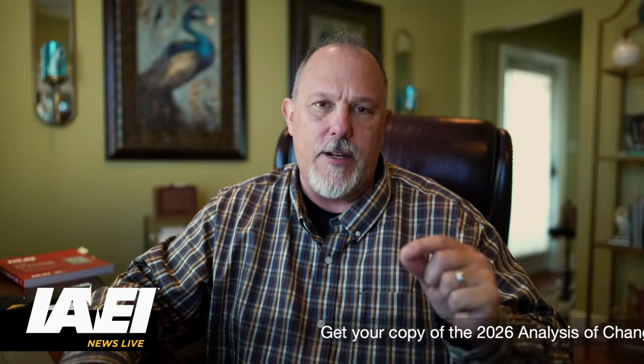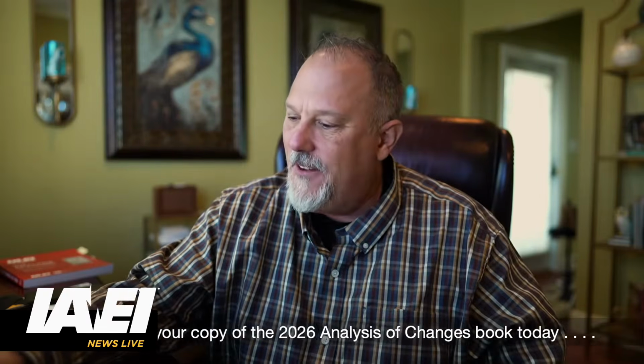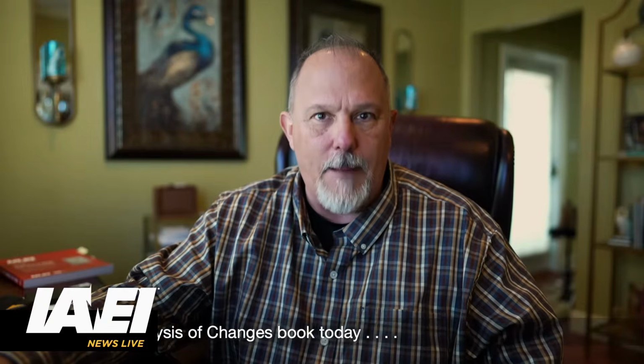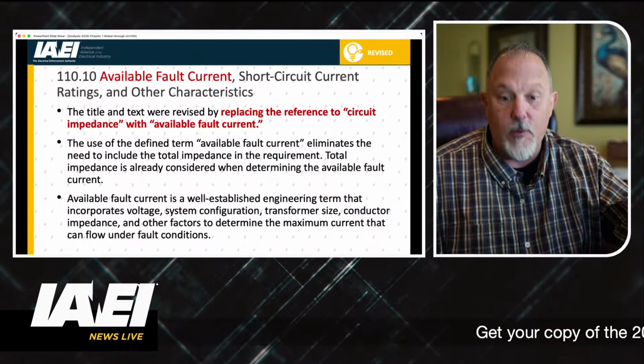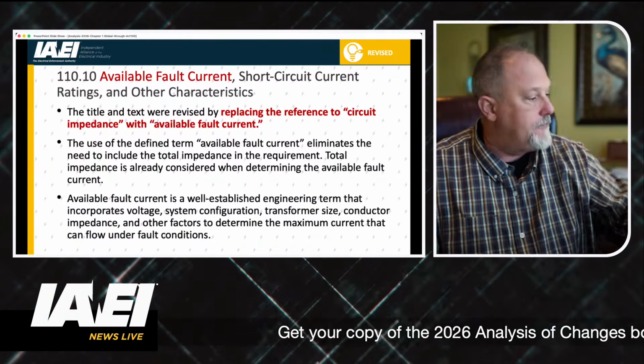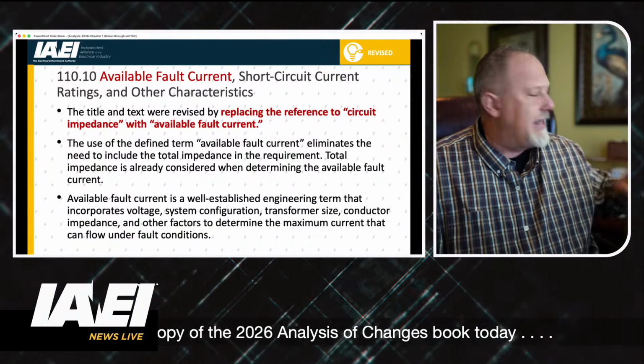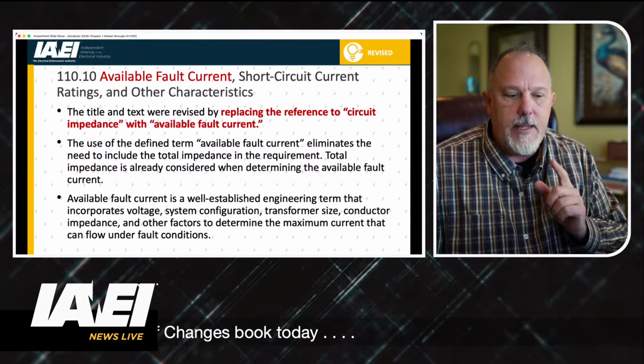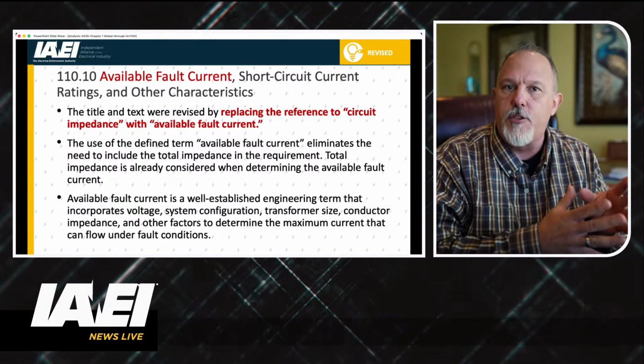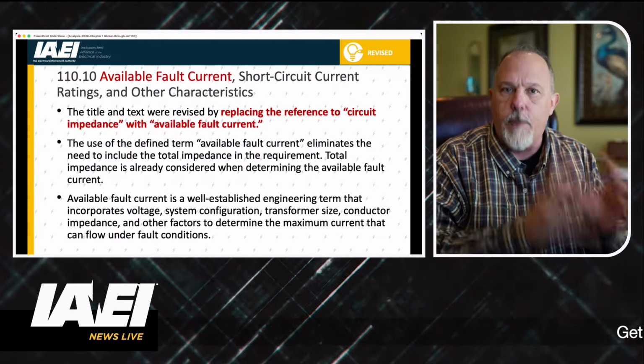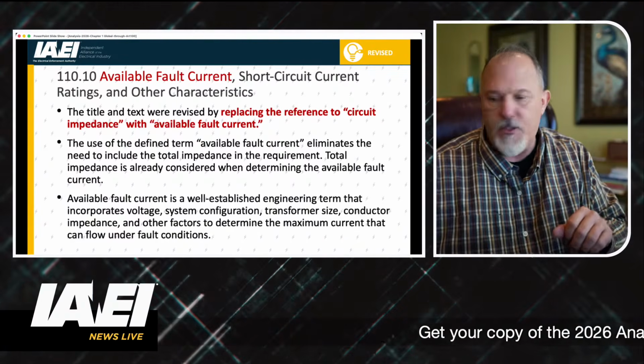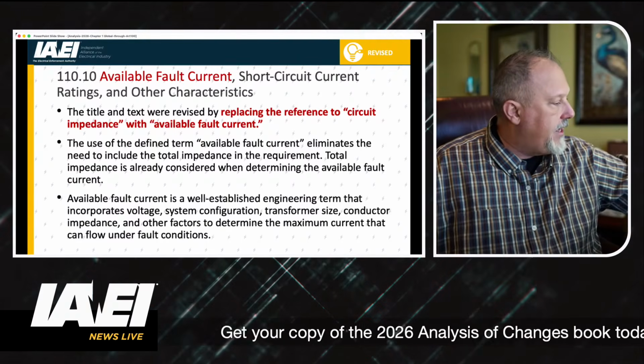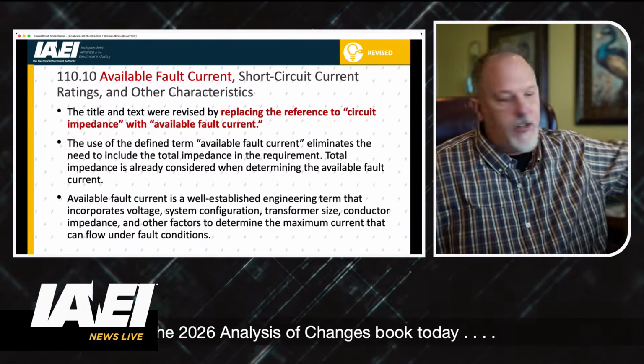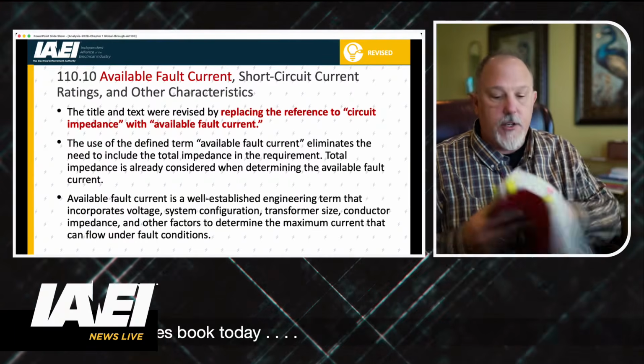I don't know if there's much to talk about here in 110.10. Remember, I feel like I covered this material before, which I probably did at an IAEI meeting. But 110.10 was the section that we always reference with regard to short circuit current rating. And what we would say is that you can't violate 110.10 when we get to short circuit current values.